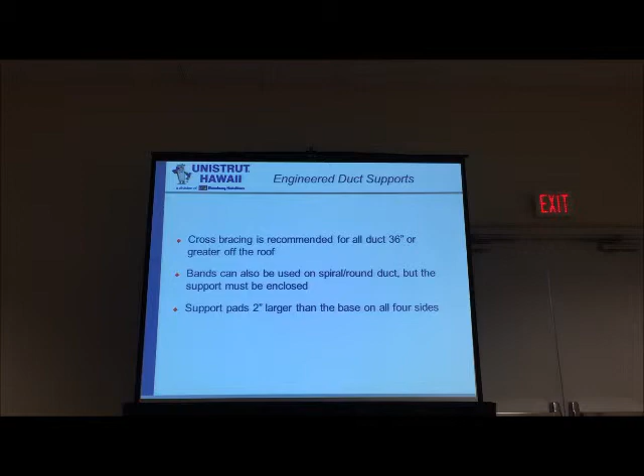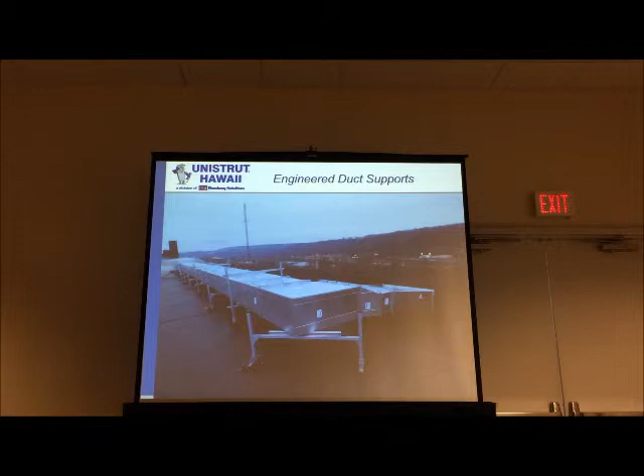Some pictures of that. Here we go. We have a picture that does show the bracing. You can see right here, there's bracing between this vertical and this vertical, because this duct will move and cause movement here, so the braces are added so that this foot doesn't start to crawl. That's part of the consideration when you are engineering MEP supports on your roof.